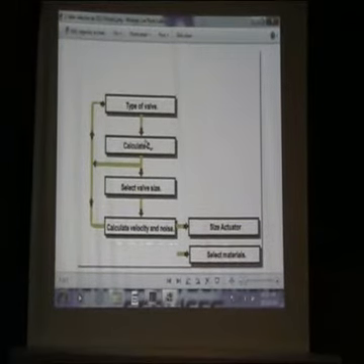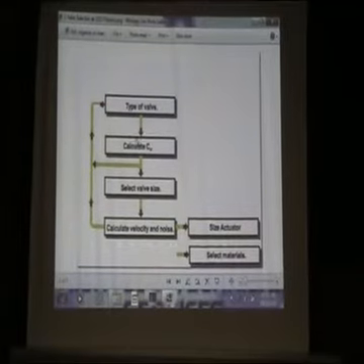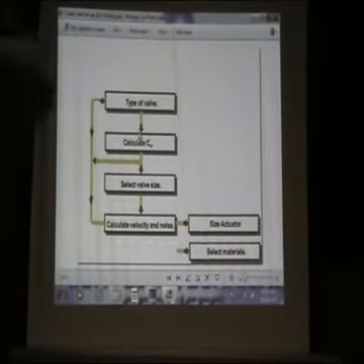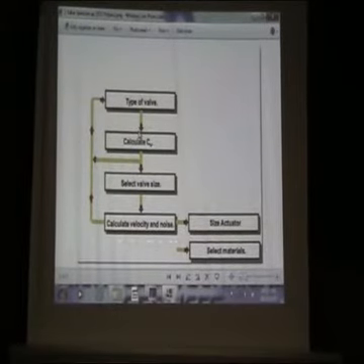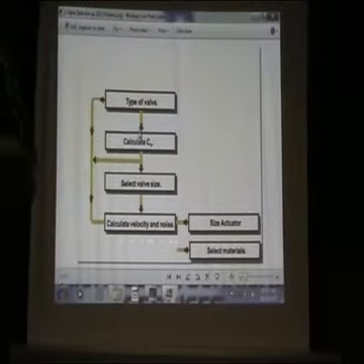Remember, that's one thing we didn't start off with, I was supposed to start off with that, which is the most important. What is the most important in selecting the type of valve? What do you need to know? I want to design a plant now. You need to know what the pressure is. That valve, remember we said this thing is limited to 10-15 bar. This thing can handle 500 bar, believe it or not.